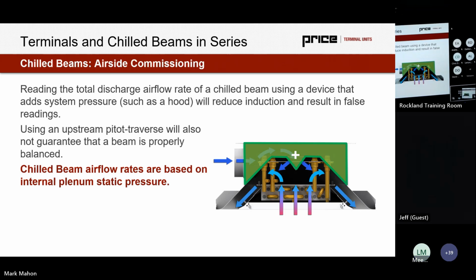One is we can't throw a flow hood in front of a beam and get an accurate measurement. Now, there's multiple reasons for that. One is it's going to add static pressure to the beam. And through adding static pressure, we're going to throw off the reading. However, more importantly, most beams, especially a 2-foot wide active chilled beam that's 24 inches wide like we're seeing here, it's bidirectional. And the beam's not able to actually grab that airflow properly, and we're not going to get a measurement this way and a measurement that way and know that it's accurate. So chilled beams are not tested nor balanced by utilizing a flow hood.